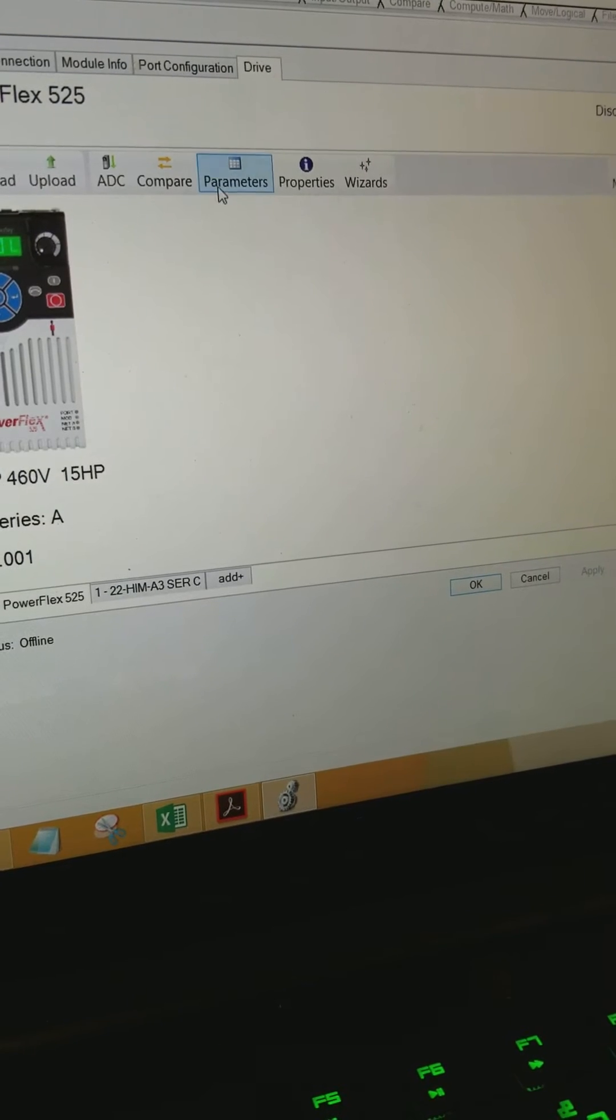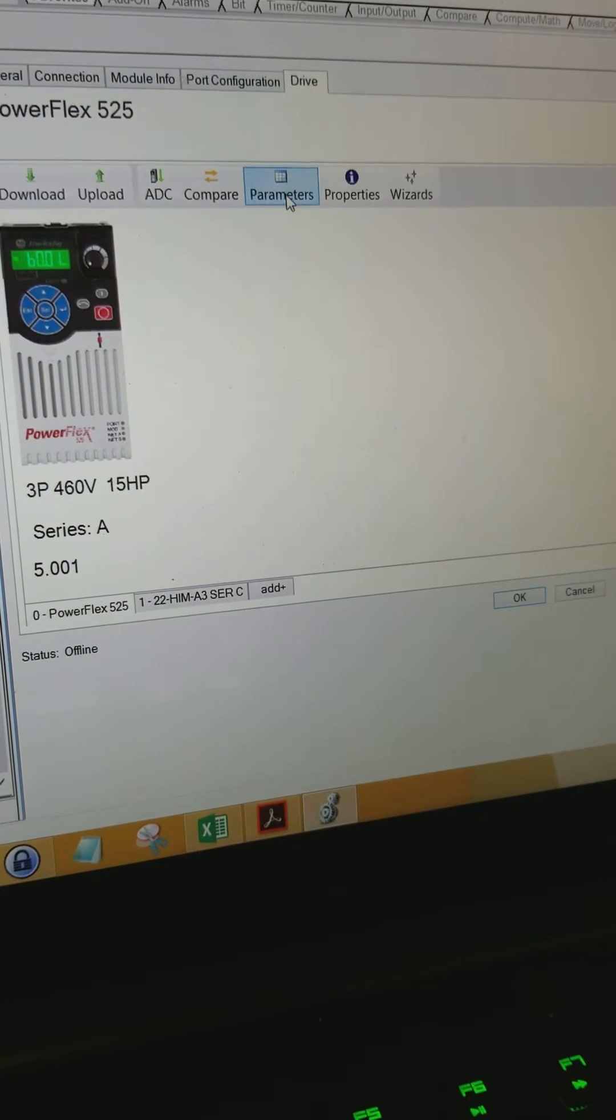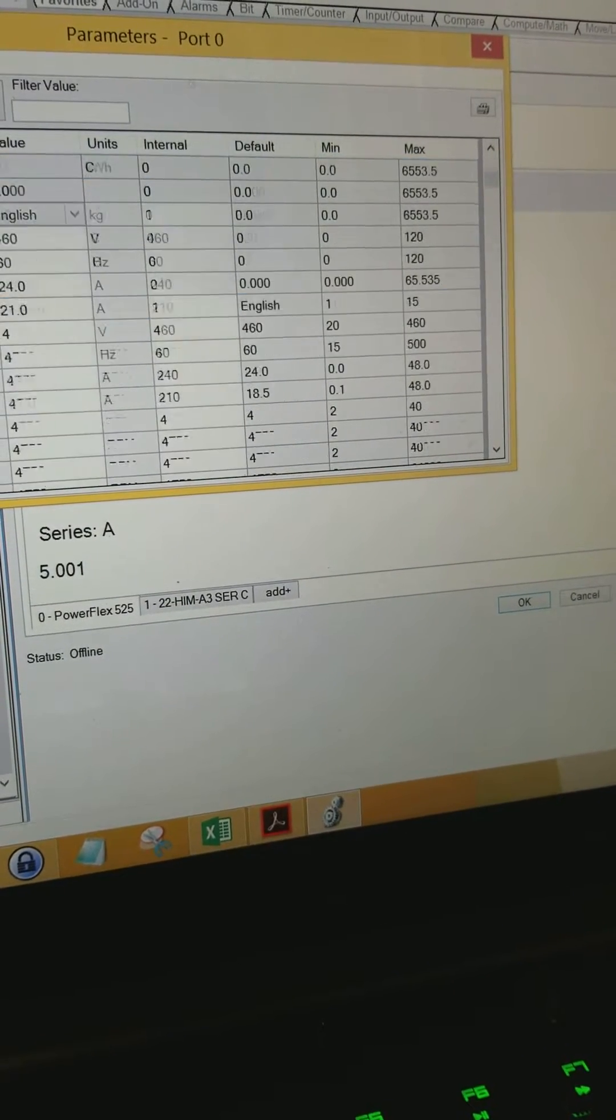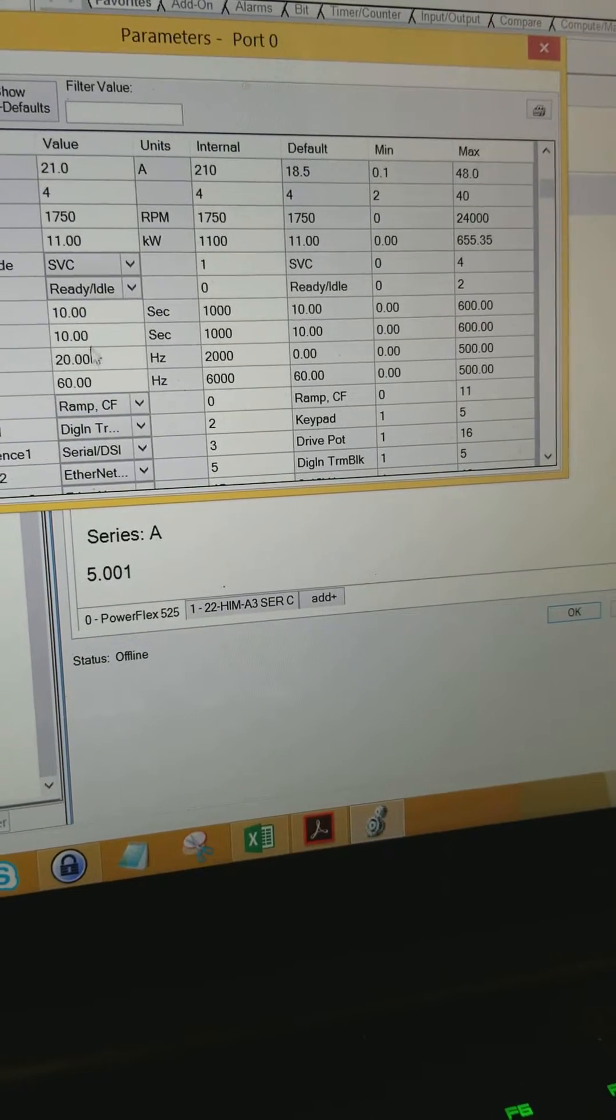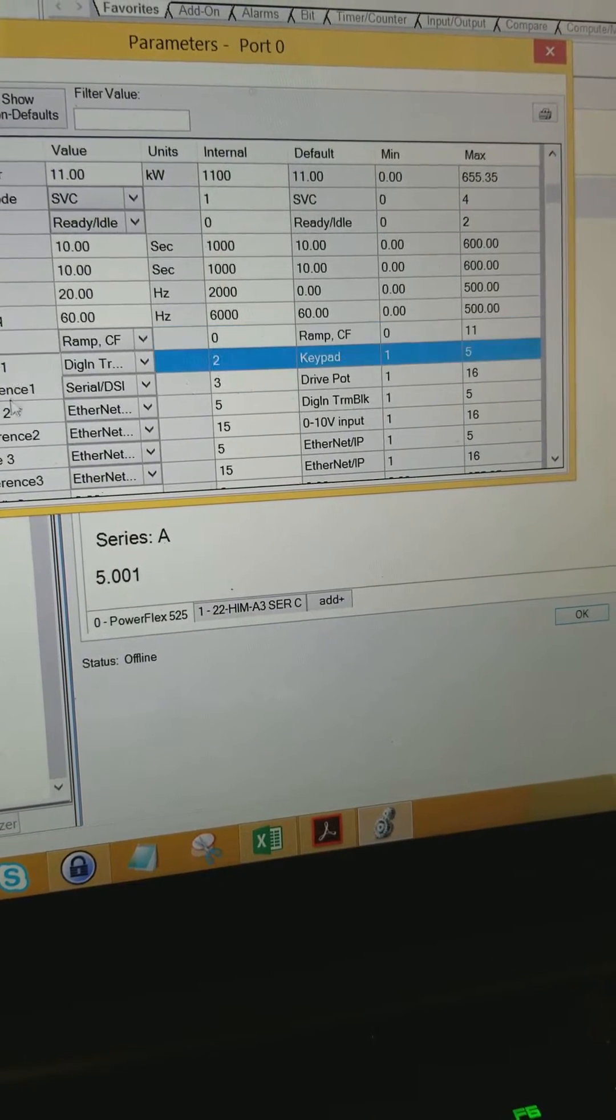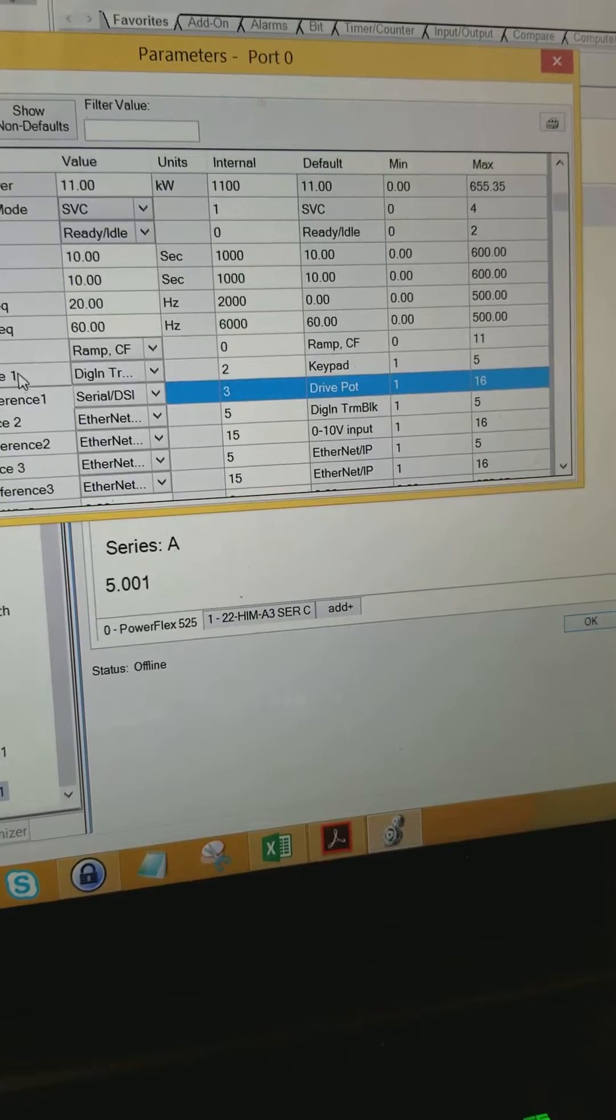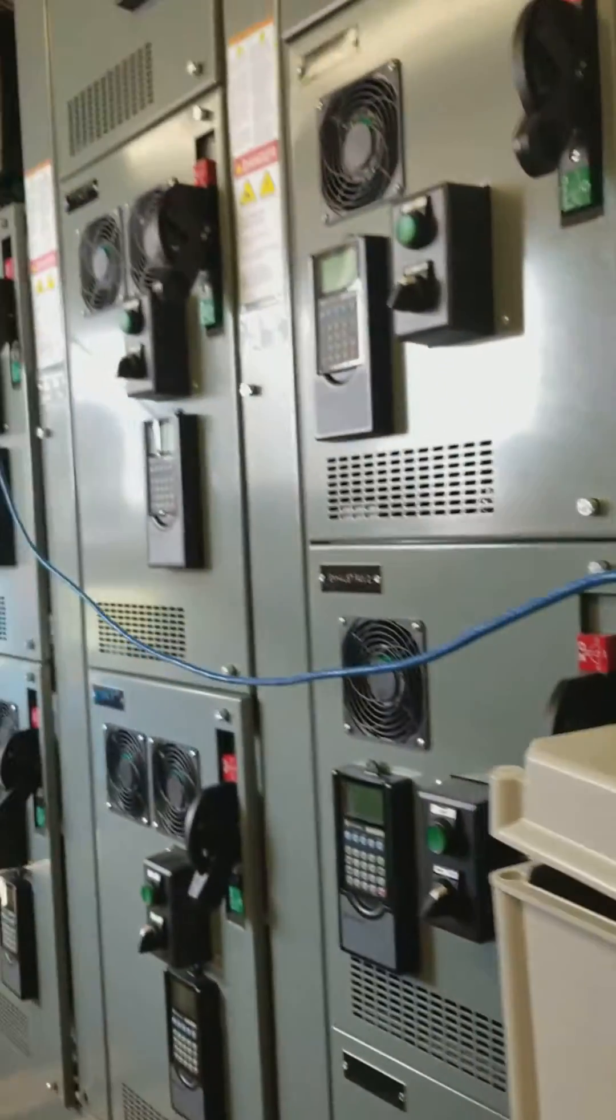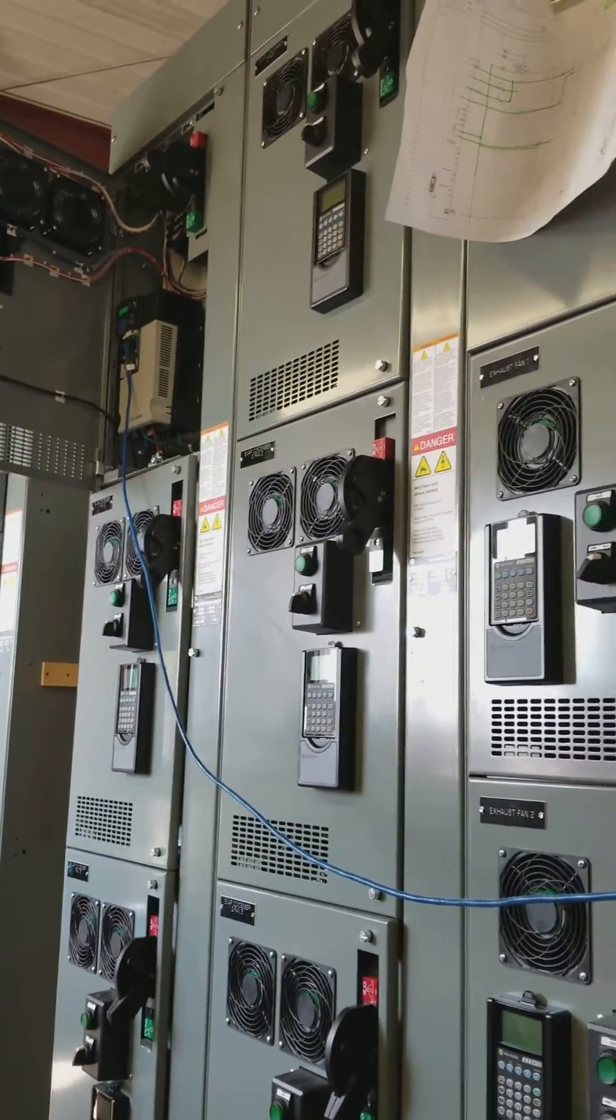And previously I've already set all these parameters that I needed for the drive to work the way I want it to. Set a minimum frequency in my different start sources. So first source will be, I have a handoff auto switch on there. So in hand it'll just go off of a keypad reference.